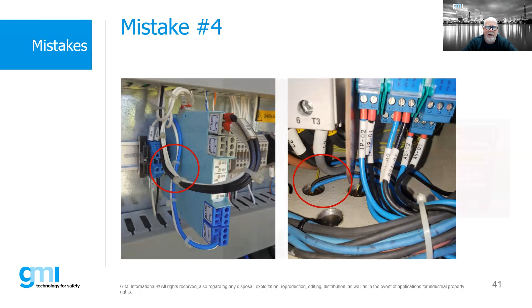Same thing when we look over on our left-hand side, we have our incoming power going to the barrier, we have our outgoing, but what have we done? We've brought them basically together at this particular point in time. So be aware, when we're doing intrinsic safety, we need to make sure that we keep this separation of IS and non-IS.